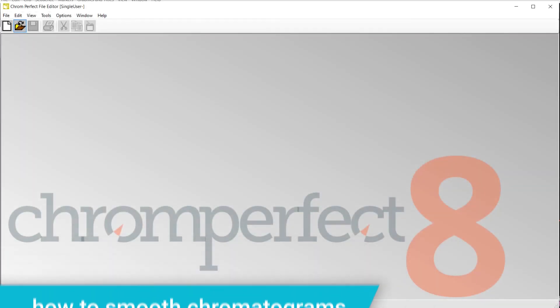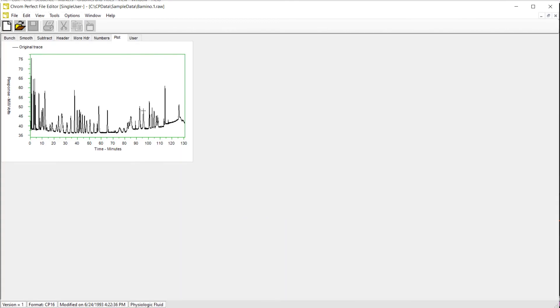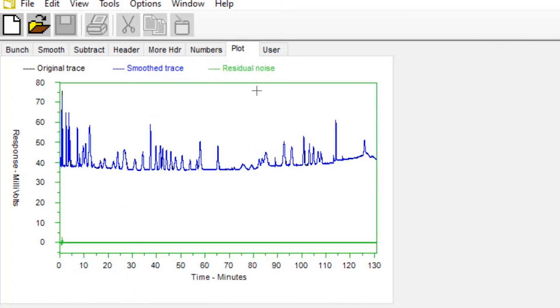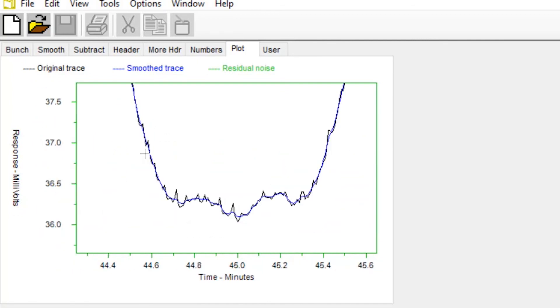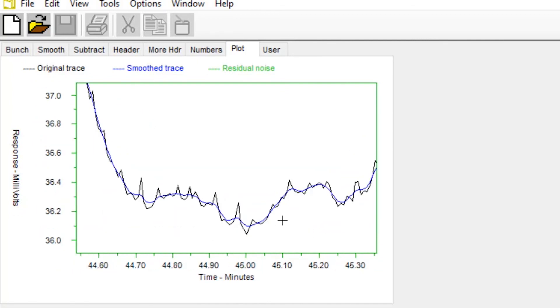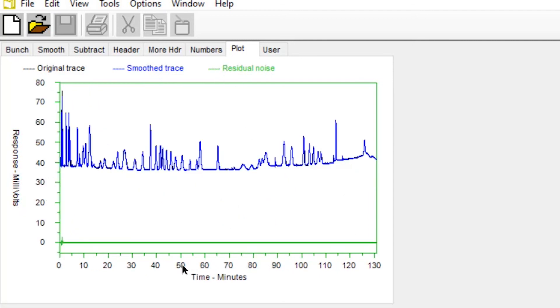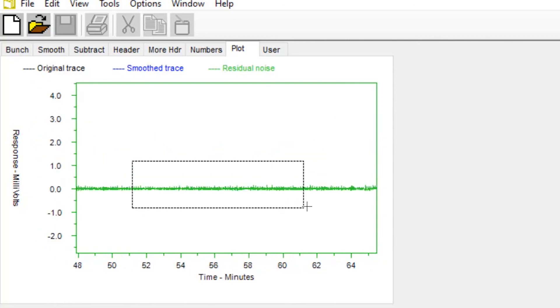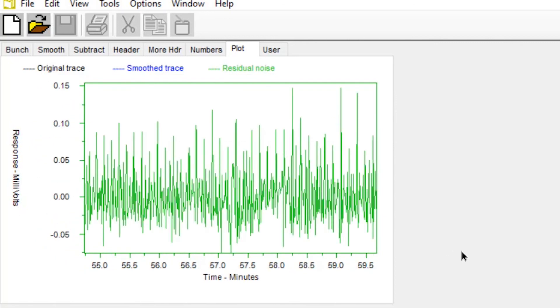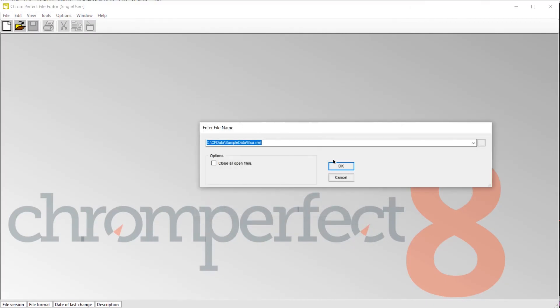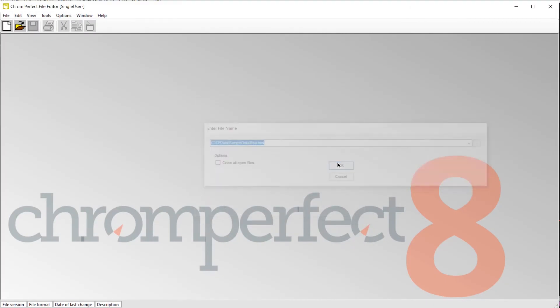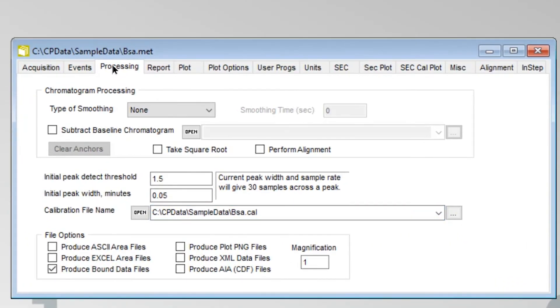How to smooth chromatograms. Individual RAW files may be smoothed manually within the RAW file editor. This is the best way to become familiar with the effects of smoothing. Here it is possible to repeatedly smooth the same chromatogram. Multiple linear smoothings are cumulative in their effect, but multiple non-linear smoothings are not. If a chromatogram has already been subjected to median smoothing, then further median smoothings with the same or a smaller smoothing time will have no effect whatsoever. Once a suitable smoothing algorithm and the appropriate smoothing time have been determined, these choices may be put in a method file.